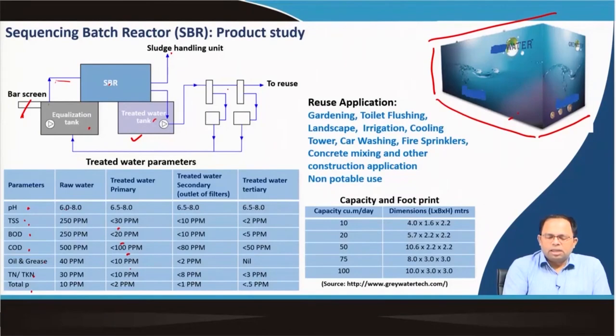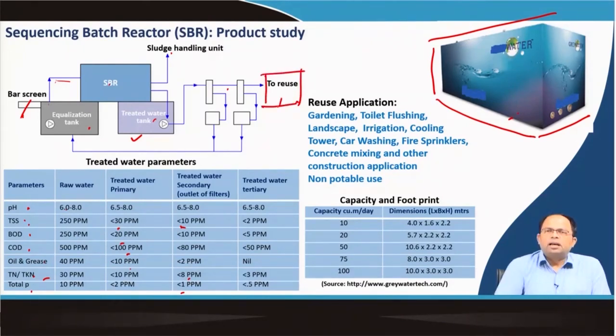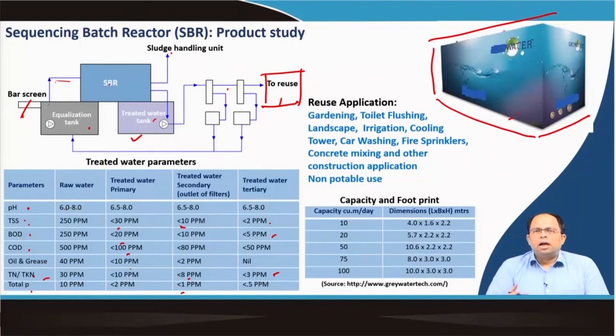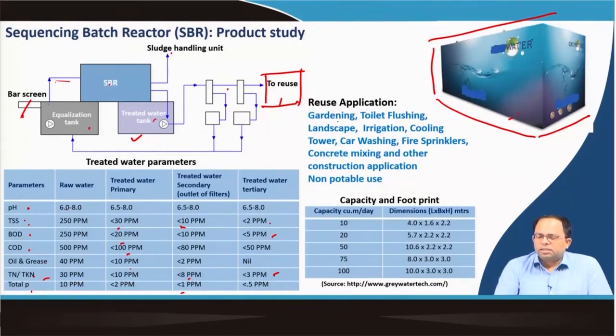After secondary filters, TSS reduces to less than 10 ppm and nitrogen to less than 8 ppm. With further tertiary treatment — adding a filter — TSS can be reduced to around 2 ppm, BOD less than 5 ppm, and nitrogen less than 3 ppm, which more or less meets discharge standards. This water can be reused for gardening, toilet flushing, landscape irrigation, cooling towers, car washing, cooling towers for air conditioners, fire sprinklers, concrete mixing, and other construction applications — mostly for non-potable use.